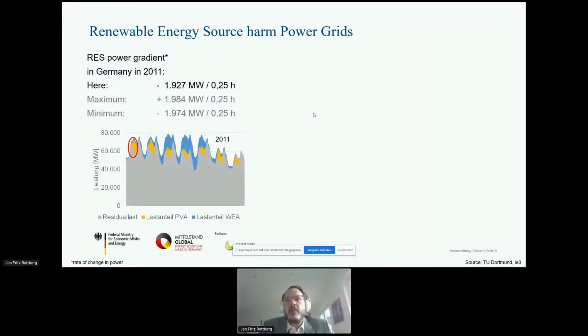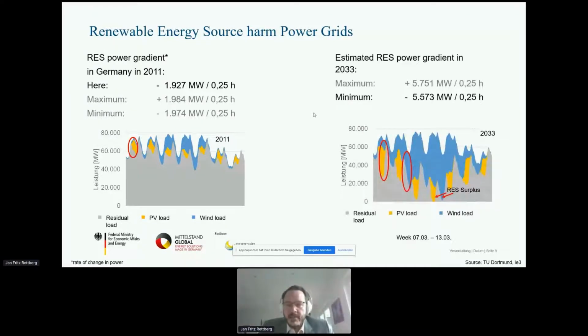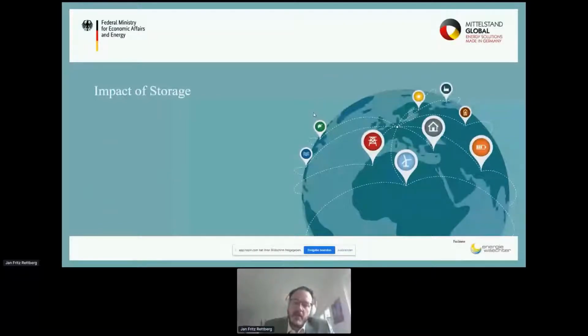When estimating our renewable expansion plans for 2033, we're talking about a power gradient of more or less 6,000 megawatts in a quarter of an hour. At the bottom of the graph, we see times where the residual load means conventional power plants have to switch off totally, where we have a surplus of renewables. We'll only manage these situations when we have enough storage. So the impact of storage could be to help stabilize our power grid.